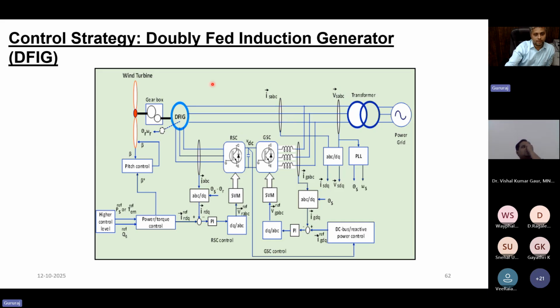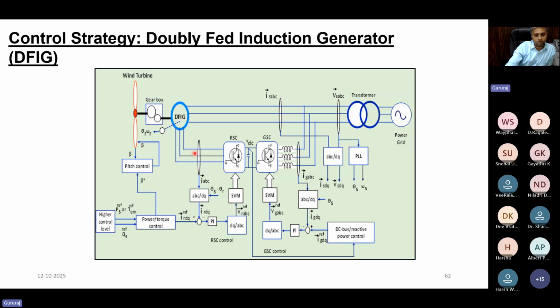So there is a DC on the stator now, and there is a rotor rotating at close to synchronous speed. So the relative speed variation is quite high, and because of the flux cutting principle, a dynamically induced EMF of high magnitude is seen on the rotor side. That will induce a huge current flowing through the switches, because of which the switches may blow off, because the converters are meant to carry only 30% of the capacity as compared to the stator side.